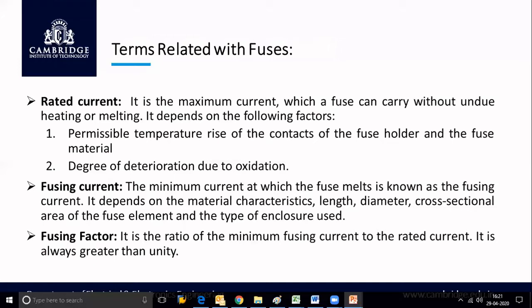Now, what is meant by a fusing factor? Fusing factor is the ratio of the above two currents. That means it is the ratio of minimum fusing current to the rated current. That is, fusing factor is equal to fusing current divided by rated current. Because the fusing current is always greater than the rated current, the fusing factor is always more than unity. And because it is a ratio of two current values, the fusing current and the rated current, it does not have any units. So these are the three important terms we need to understand when we are talking about a fuse.